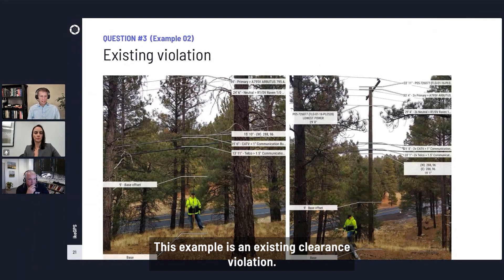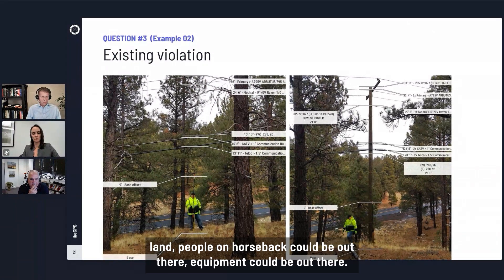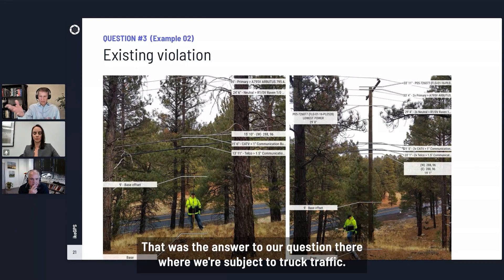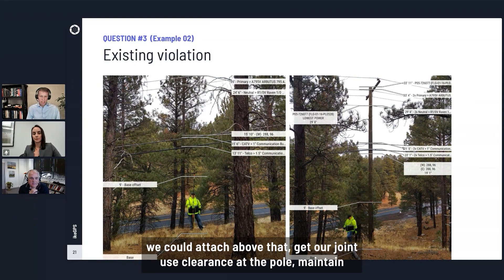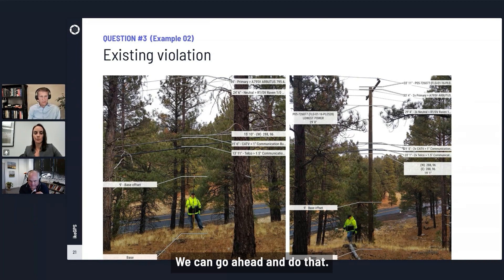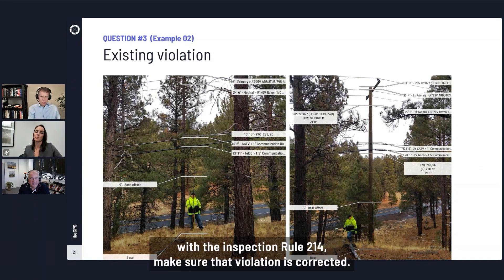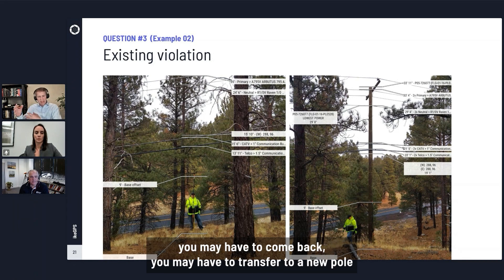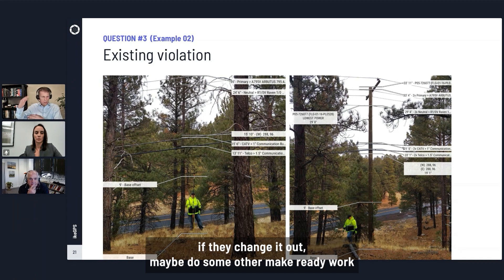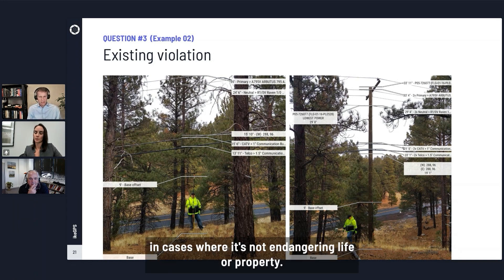This next example is an existing clearance violation — you can see on the left there's a 13-foot 11-inch clearance in forest land where people on horseback or equipment could be out there, but we have to meet 15 and a half feet where we're subject to truck traffic. If we could attach above that — there looks like some room — we could attach above, get our joint-use clearance at the pole, and maintain our clearance above ground with a new fiber or communications cable. We should notify the utility and pole owner, who will hopefully follow up with inspection under Rule 214 to get that violation corrected.